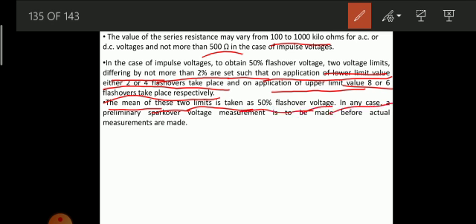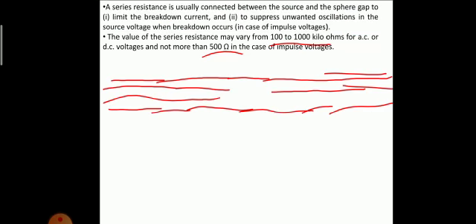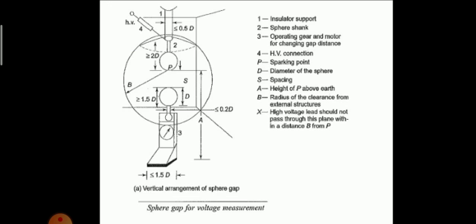So in any case a preliminary spark over voltage measurement is to be made before actual measurements are done. What I mean is, for AC and DC voltage measurements, it's a simple technique. Here between the two spheres we apply the voltage which is to be measured. As soon as flashover occurs, that is the breakdown voltage, we say.